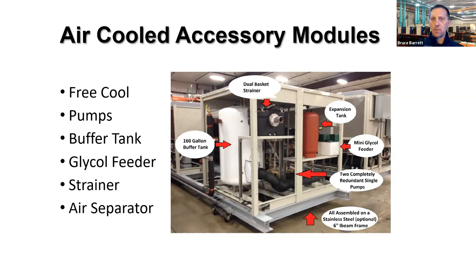This one happens to have two completely redundant single pumps. We'll basically use any pump manufacturer, whatever your preference is. These are mounted all on a steel base, so we can configure the entire chiller, the entire system, and drop it right on the ground. A single point of power becomes plug and play for your contractor versus assembling everything on site, putting out different bids for all the different components. We can gather that all up into one package.